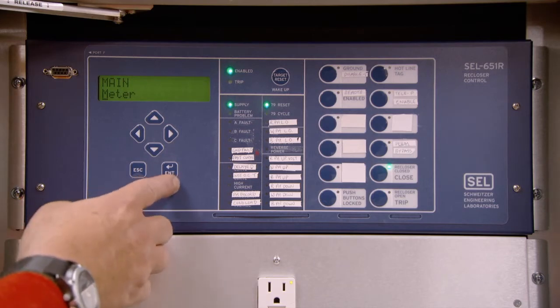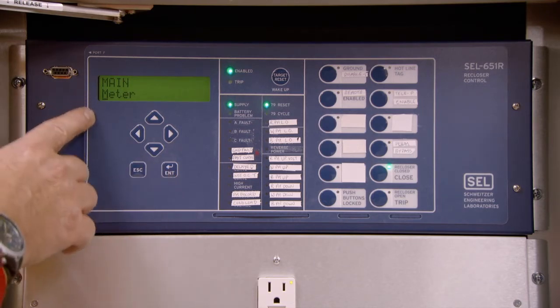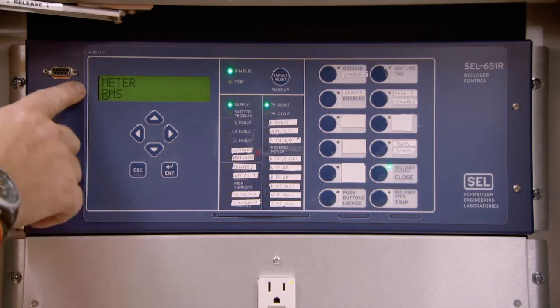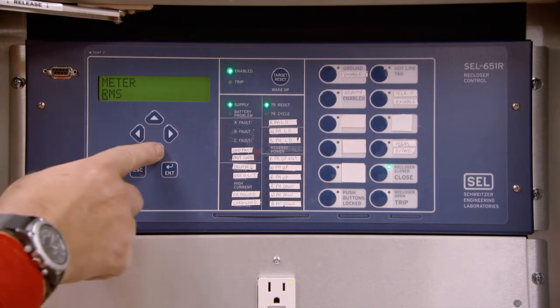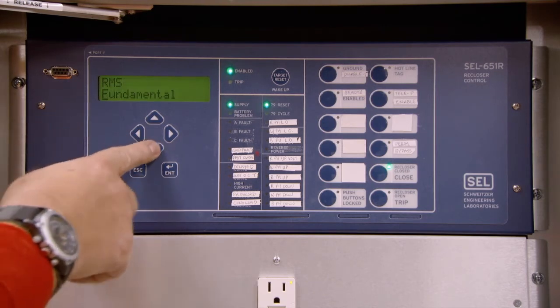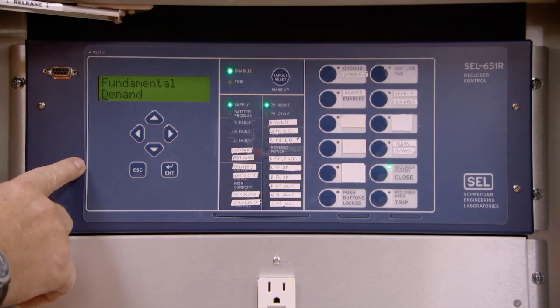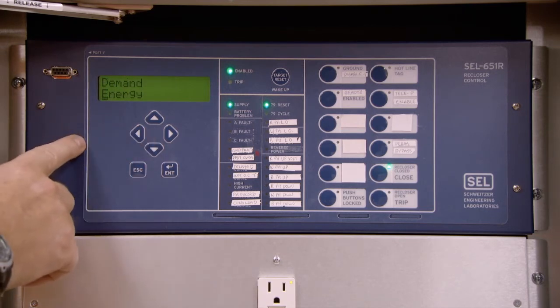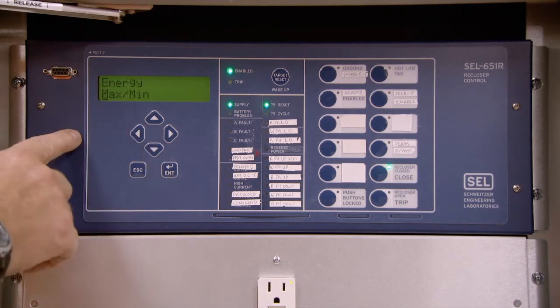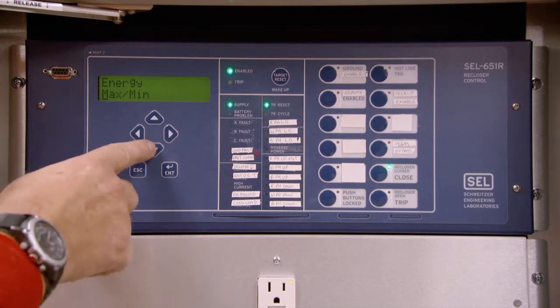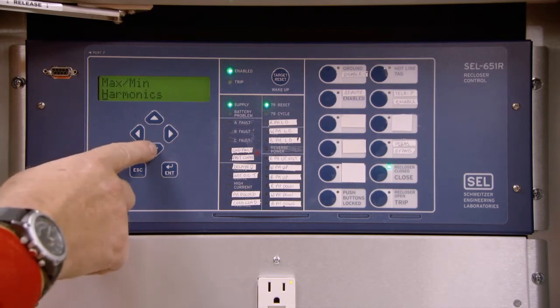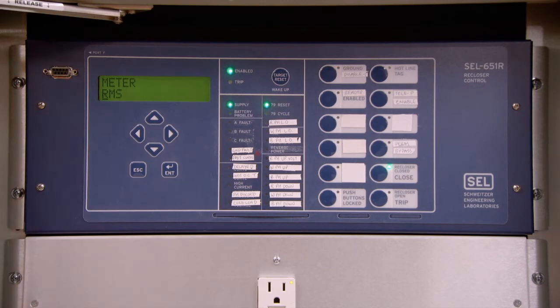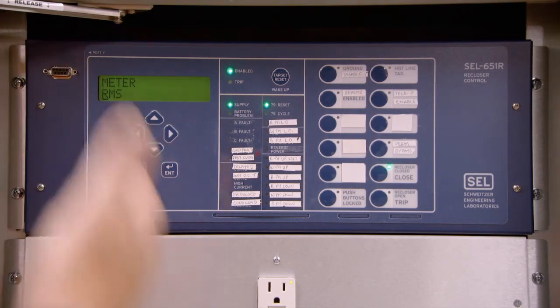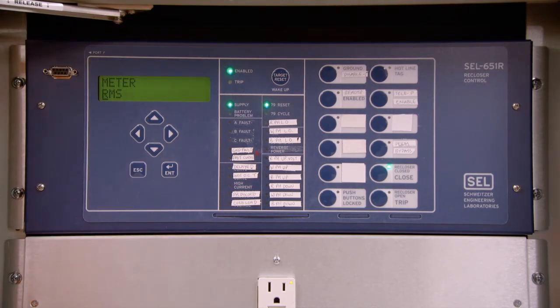In the Meter menu, if you press Enter, you can view RMS metering, Fundamental metering, Demand metering, Energy, Minimum and Maximum, and Harmonics. Once the meter menus have cycled through, the scrolling screen will return to the beginning menu of RMS metering.